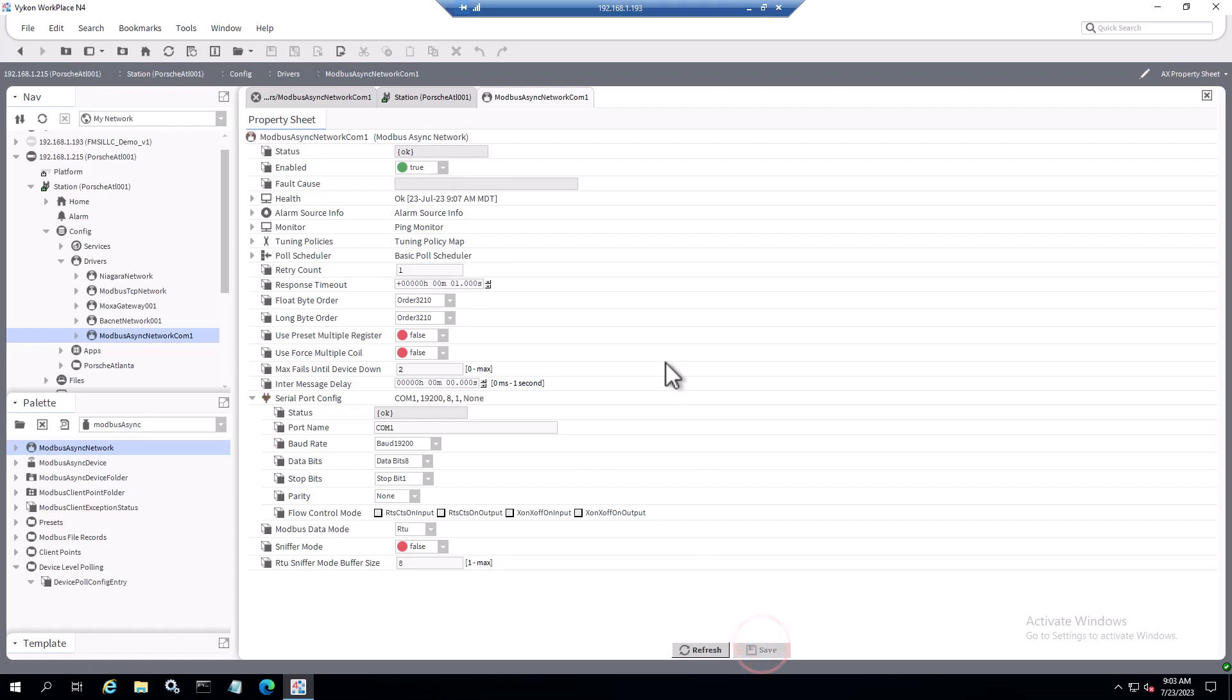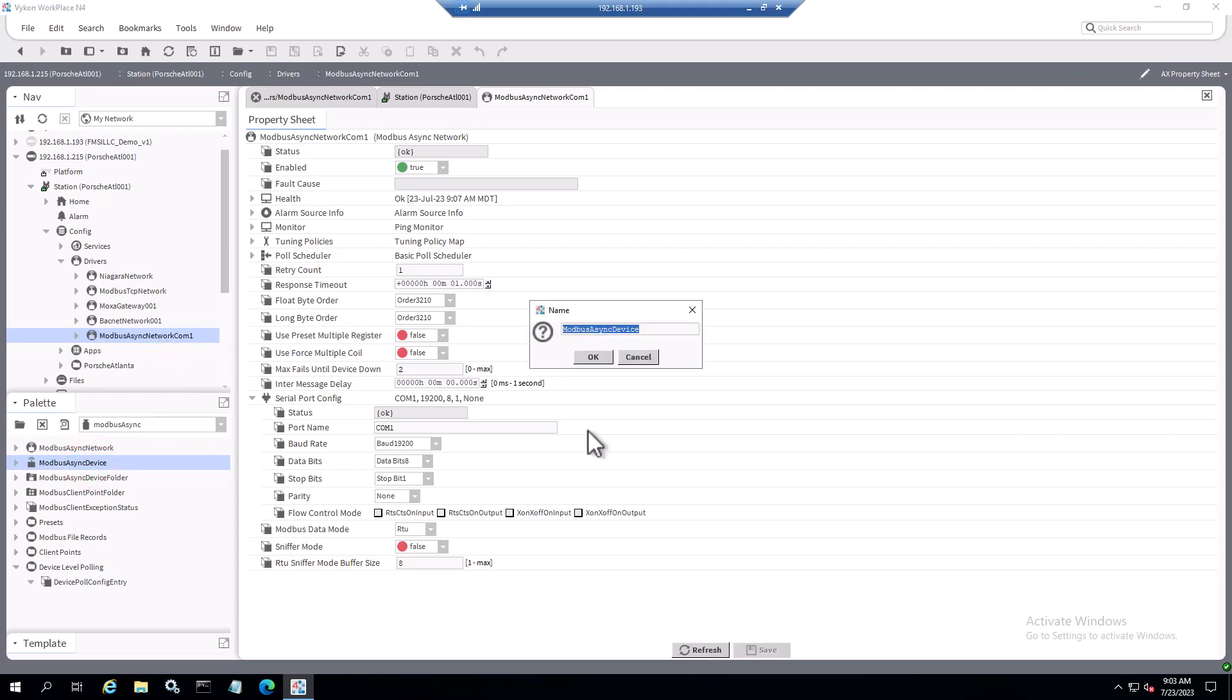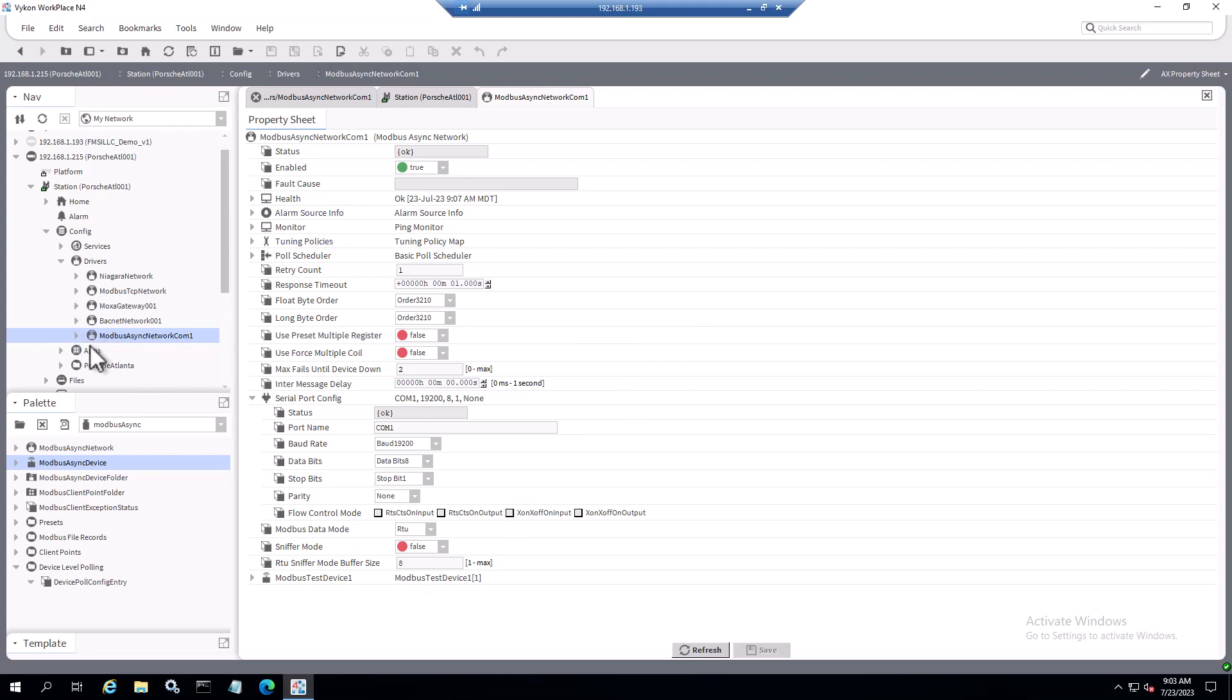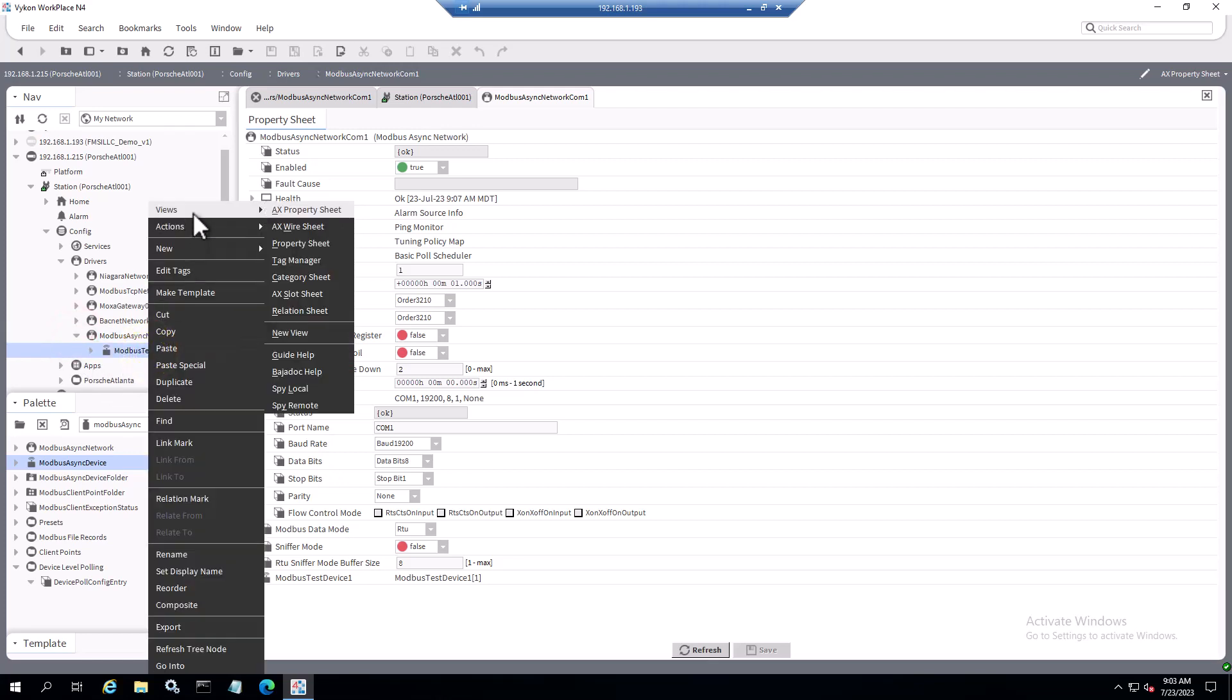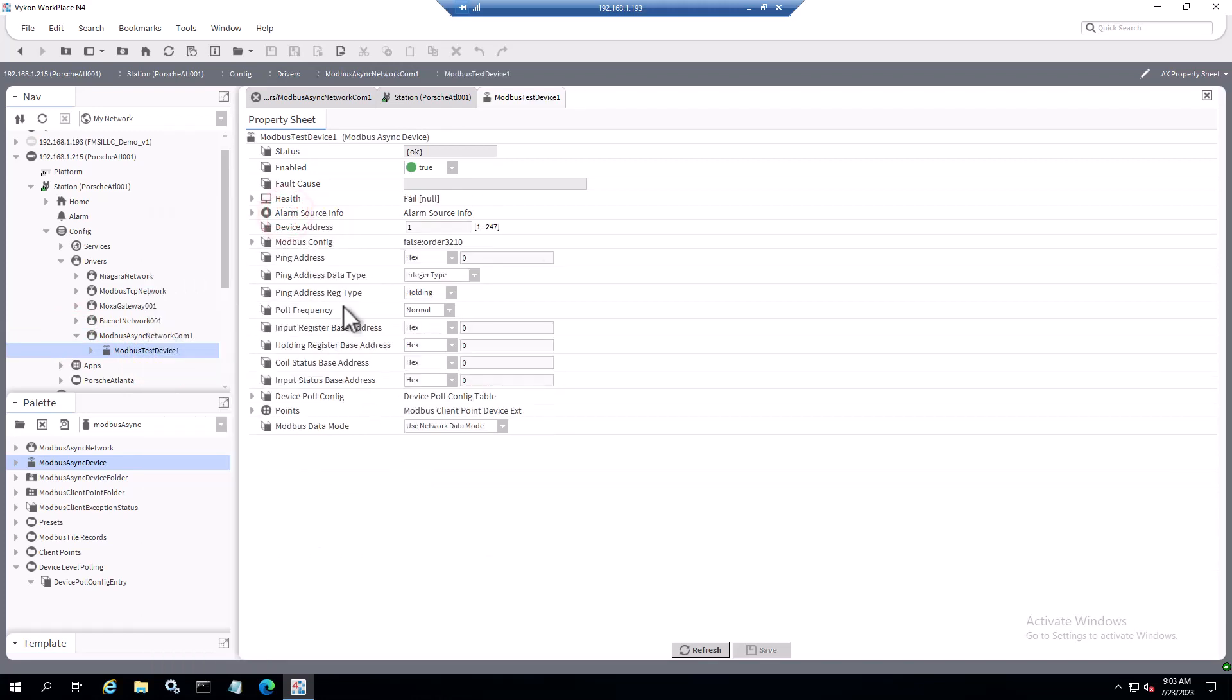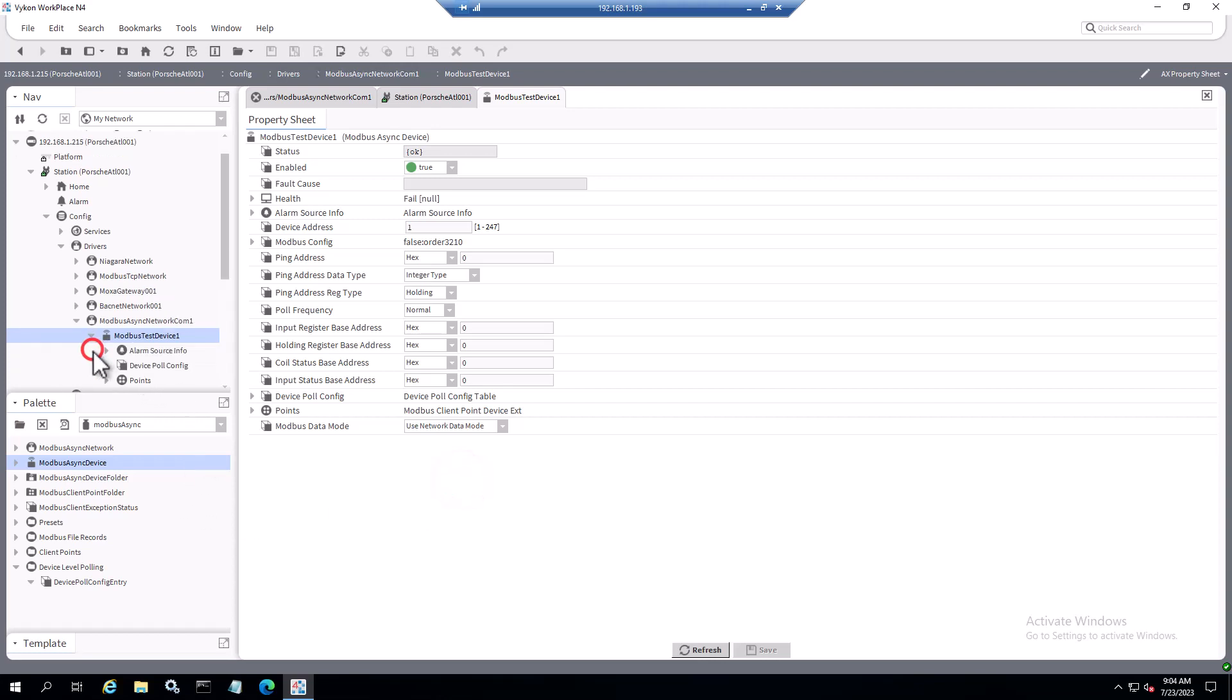On the other end of the serial line hooked to COM1, I'm using a USB to RS485 converter and then using a program from Modbus Tools called Modbus Slave. What I'm going to do here is make a test device. If I go back to the palette and left click on Modbus async device, I just have to grab that, drag it up, drop it here. I'm just going to call it test device one, click OK. Now we see we have our device listed. I'm going to expand this and select that, go to the ax property sheet. Based on the simulator I'm going to be testing using device ID or slave ID 1, so that is set correctly.